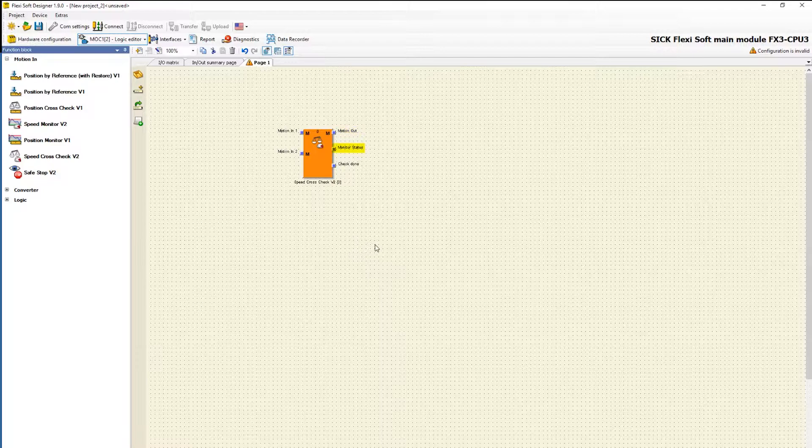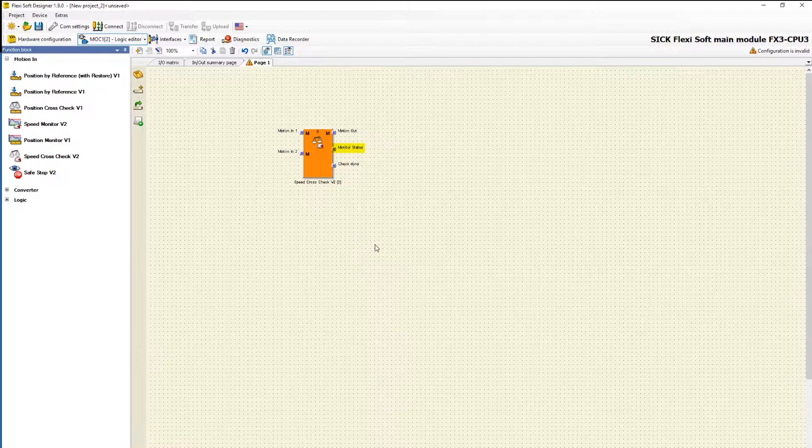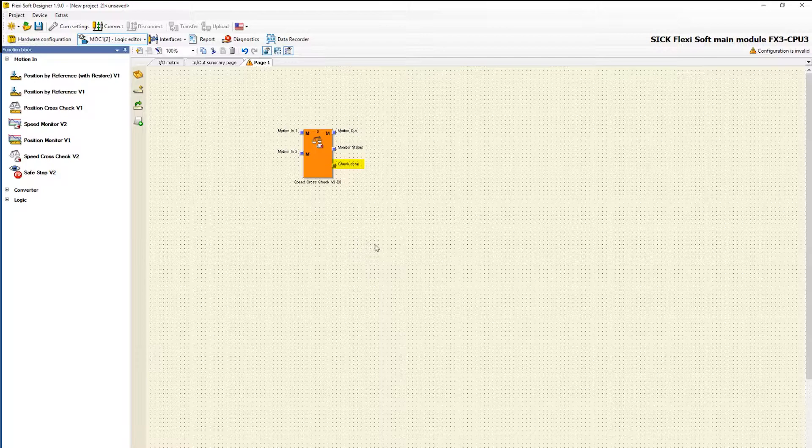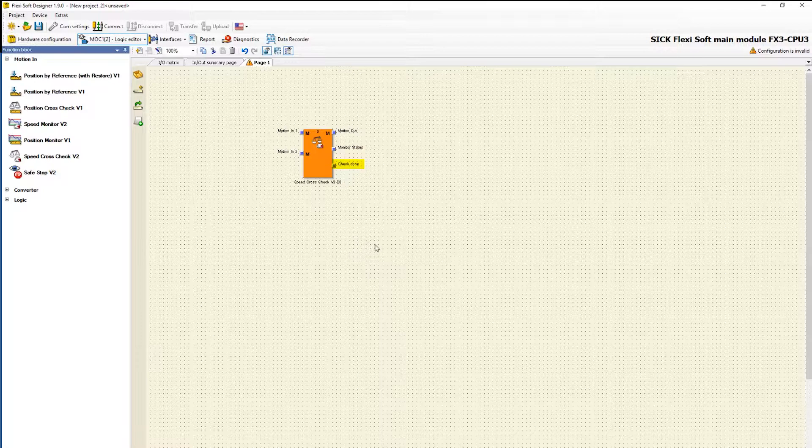Monitor status indicates whether the speed cross check function has failed. If an error occurs the status bit changes to 0. The output check done switches to 1 when a cross check is performed for the first time and switches back to 0 if one of the motion in data is invalid.